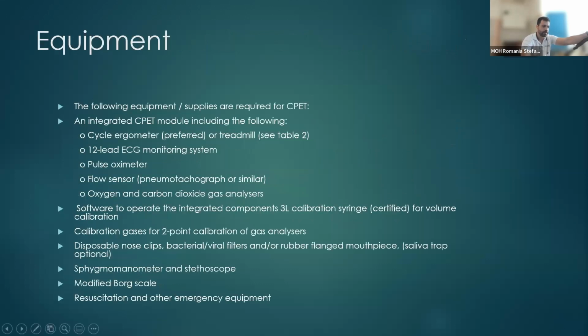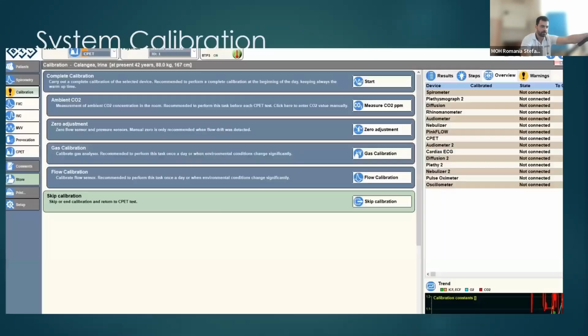terminate the exercise testing. In terms of the equipment that we are using for the cardiopulmonary exercise testing, the equipment is more complex than the basic ECG stress test, because it also has this cardiopulmonary module that is a part of the cycle ergometer or treadmill, depending on what you use. Basically, it has a flow sensor, and an oxygen and carbon dioxide gas analyzer. It has a different software that is needed for the calibration activities, and it has aspects that are related to the pulmonary evaluation. It's quite important before starting each cardiopulmonary exercise testing, as a general rule of thumb, every time you perform a stress test, to ventilate the room and to do the calibration of the device.